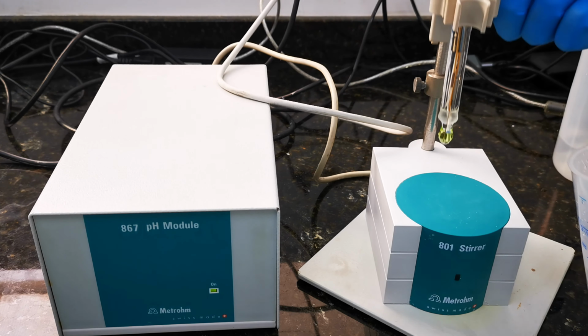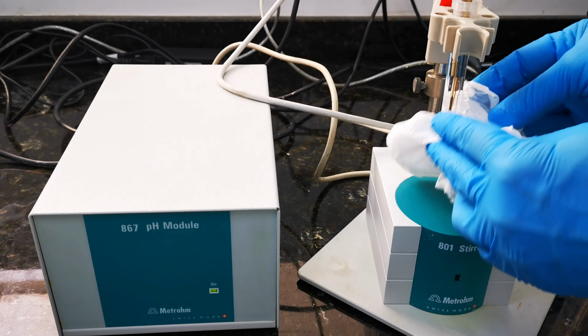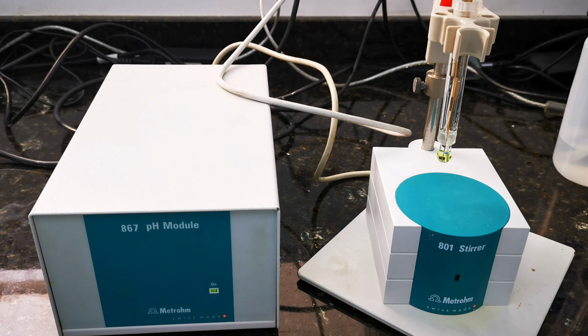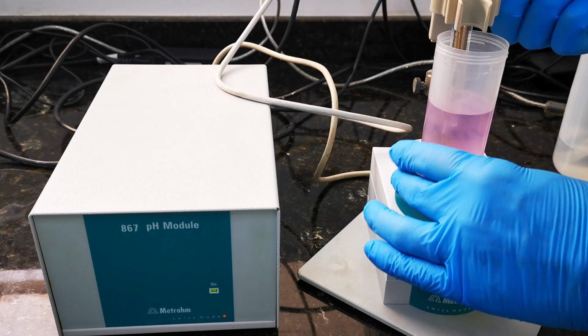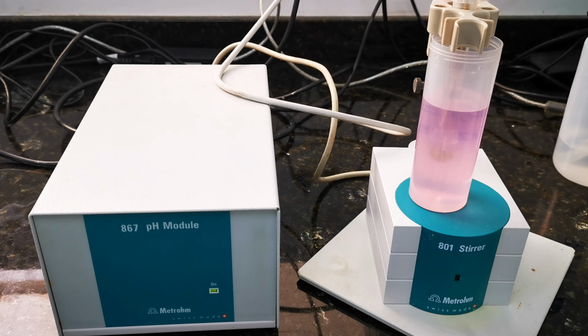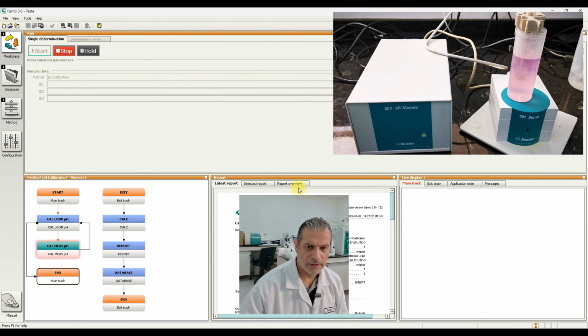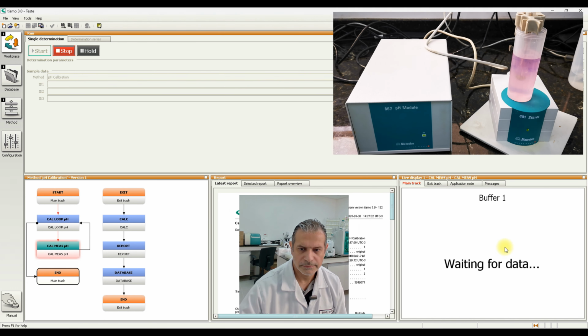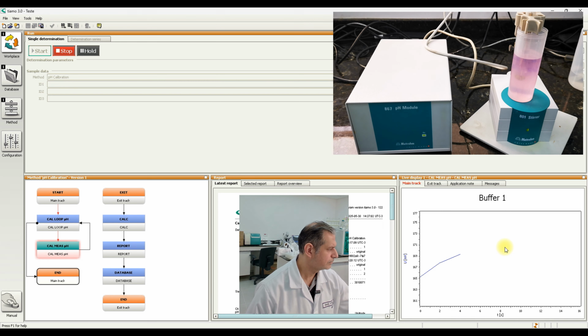Ultra pure water. You don't need to rub the electrode, just remove the excess of water with the paper. We add the pH 4, hit the OK button. And now just wait for the measurement of this buffer, the first buffer of the sequence.